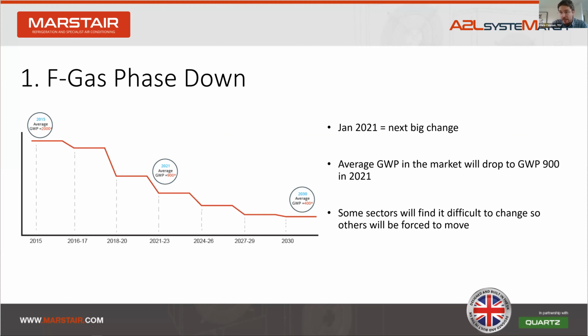Okay, so the F-gas regulation. Not going to spend too much time, but the key point is the GWP phase down and the 79% reduction on 2015 refrigerant GWP levels by 2030. This means by 2030, the average refrigerant GWP needs to be 400 if refrigerant volumes are to remain the same as 2015. Or more pressingly, there's another reduction coming at the end of this year, making the average GWP needed to be 900 from January 2021.